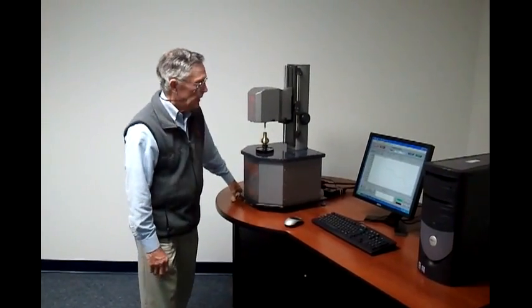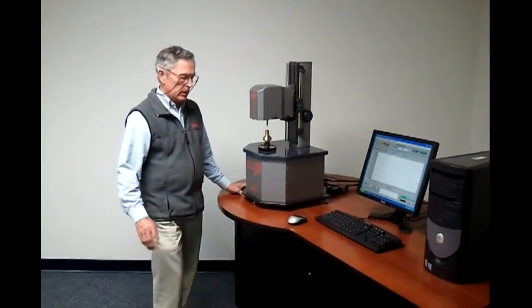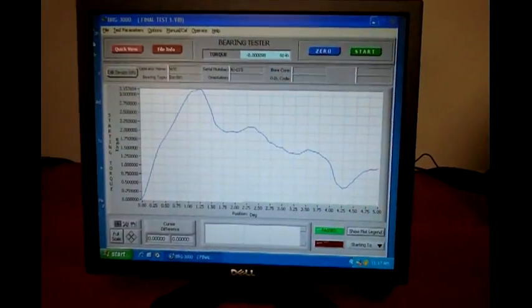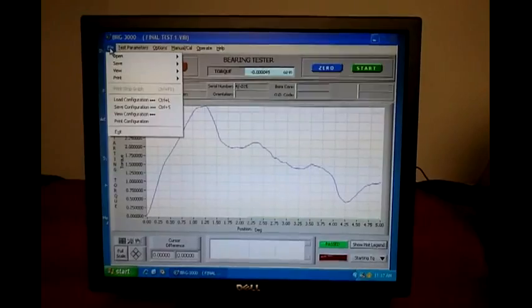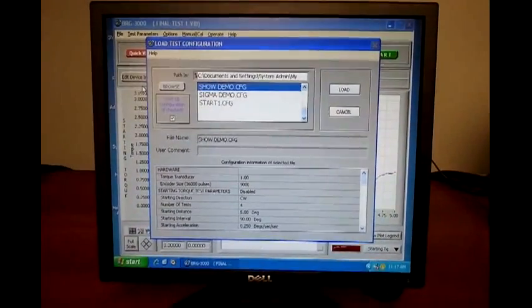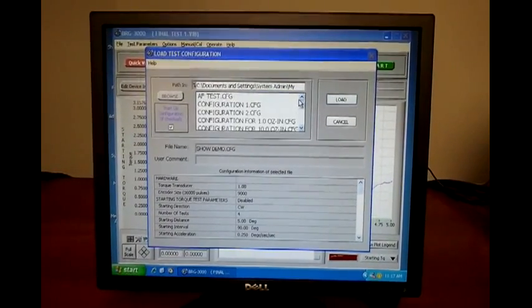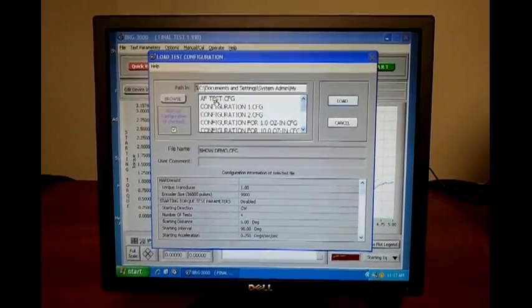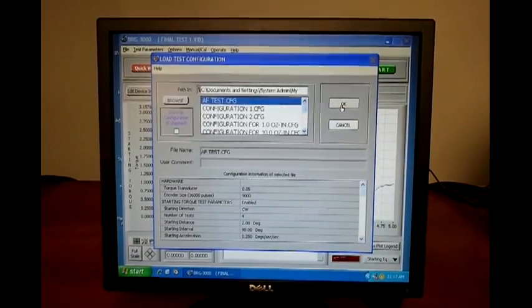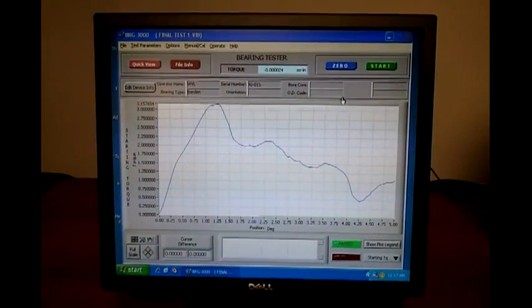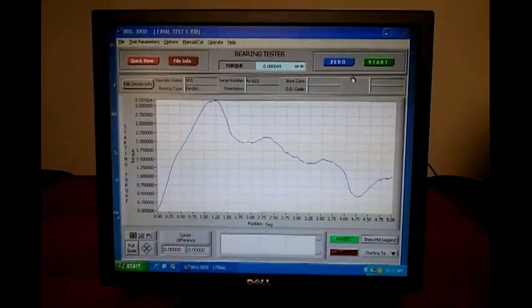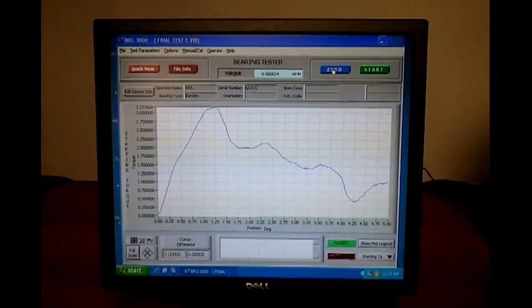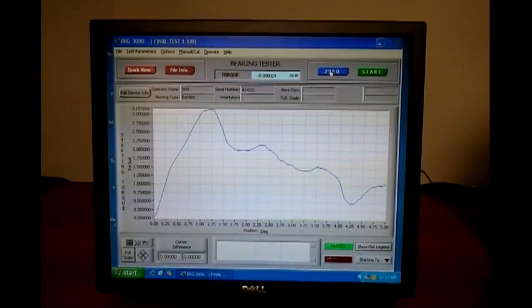Now we're going to begin phase two of this video where we will actually perform a starting torque test. First the operator comes over to the screen and selects file and load configuration. We're going to load the configuration that is correct for this bearing, which is AF test dot config. And we load that. Now we will zero the transducer, at which point we're ready to perform a test.